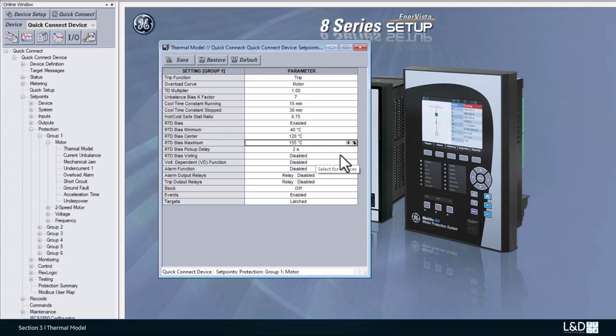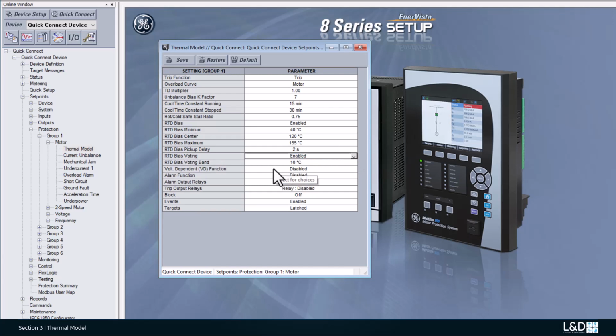There's one RTD bias voting, and this will make sure that at least 2 RTDs have been configured as a stator type. The maximum stator RTD temperature will be used by the RTD bias feature only if both the maximum stator RTD temperature and the voting RTD temperature, which is the second maximum temperature, are within the range defined by the setpoint RTD biasing voting band. Otherwise, the RTD bias feature will be blocked automatically.